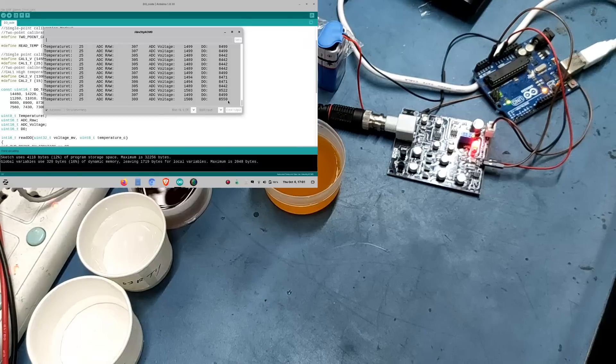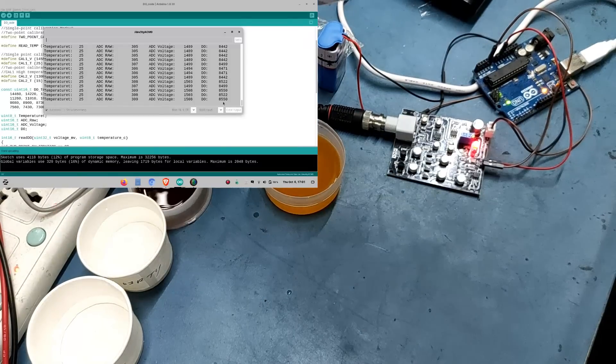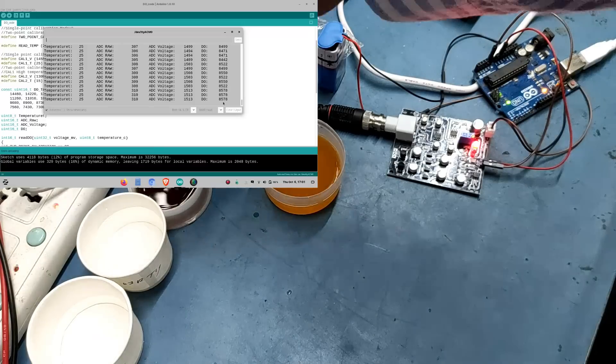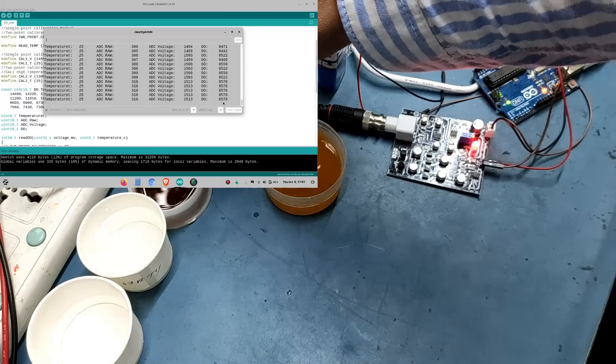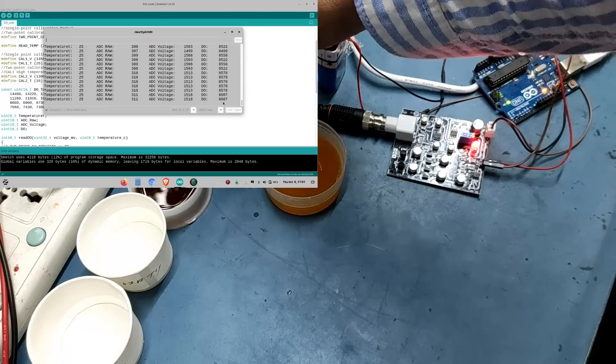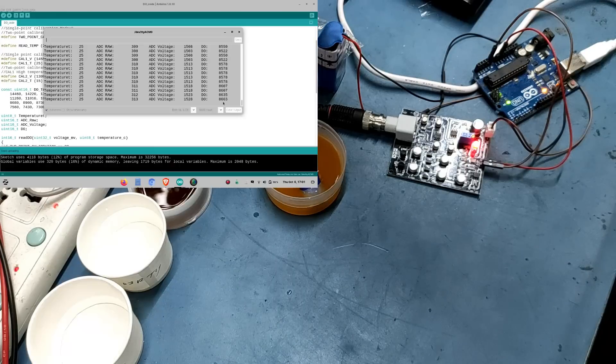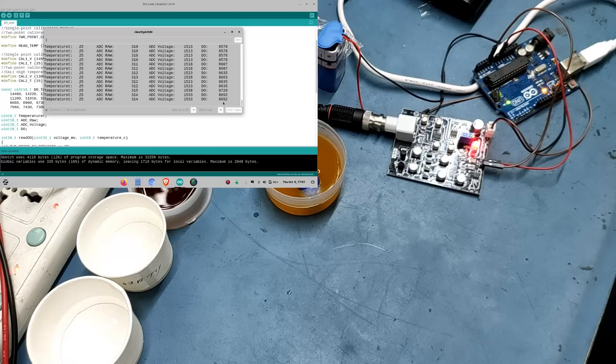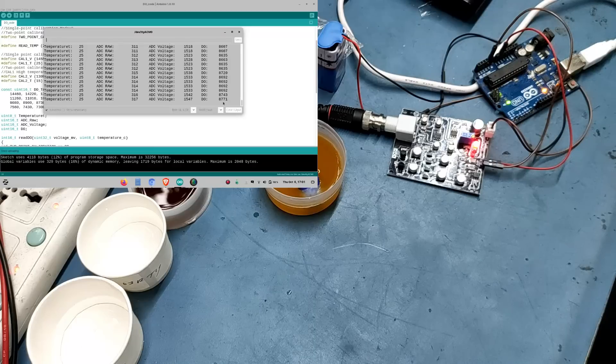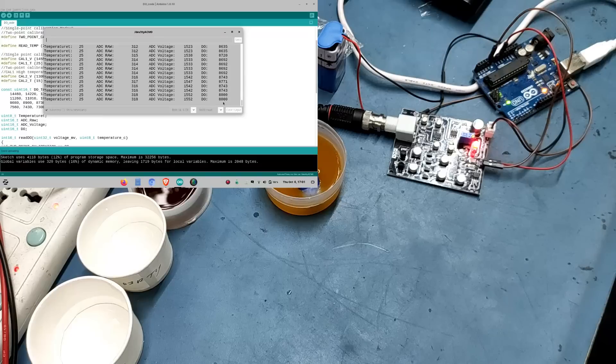Technical specifications of this product like measuring range is up to 20 ppm with a resolution of 0.1 ppm whereas the accuracy is about plus or minus 0.2 ppm. The DO sensor is made up of amperometric gold and silver membrane. The PCB signal converter board provides analog output voltages and works on 9V battery power.